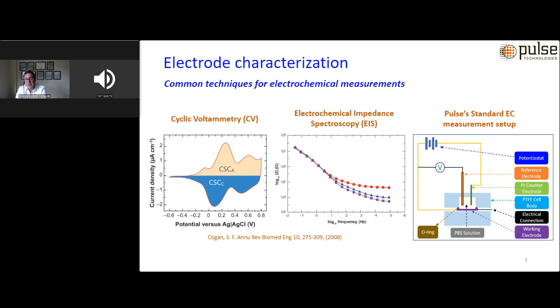Number one is cyclic voltammetry, that essentially identifies the presence of electrochemical reactions and provides information on the reversibility of reactions, and is valuable for assessing stimulation capacity and efficacy, and also the electrochemical impedance spectroscopy, which is a valuable assessment or measurement technique for recording capabilities of electrodes that measures essentially impedance at the electrode and at the interface of the electrode and the biological environment. So in our work, in order to assess the EC performance of our electrodes for comparison's sake, we use both CV and EIS measurements.